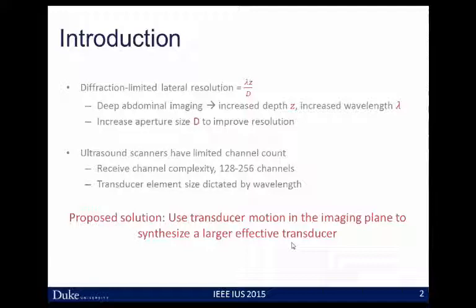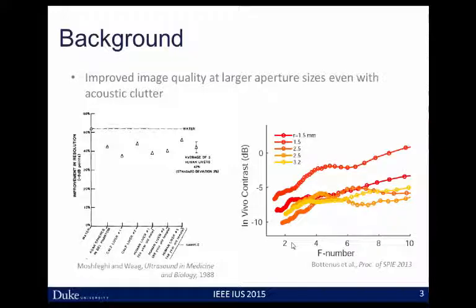Our proposed solution is to use transducer motion within the imaging plane with a conventional transducer to simply synthesize a larger effective array. In doing that, we gain the same image quality as we would have with a physically larger transducer. The literature leads us to believe we would expect increased image quality as we move to larger aperture sizes, even in the presence of acoustic clutter like we might see in the abdomen. On the left we see improved resolution looking at ex vivo liver samples as we go to a large 5-centimeter piston. On the right is some of our work showing improvements in image contrast as we increase the aperture size, looking at in vivo liver vasculature. Both of these suggest we should continue to move towards larger array sizes.